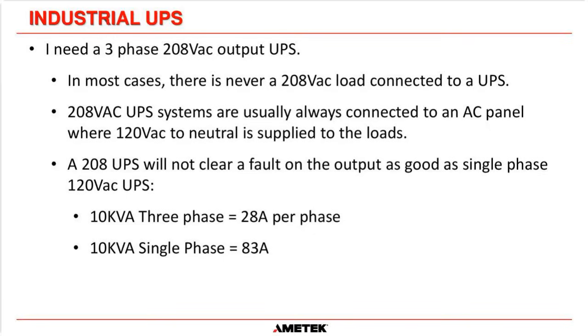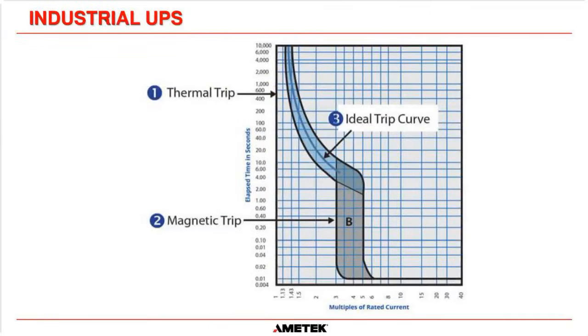Why is that important? Well, you've got to think about it. All of your load circuits are going to be protected either by a breaker or a fuse disconnect system. So let's say that the breaker protecting one of your branches is a 10 amp breaker. In both the 3-phase UPS and the single phase UPS it's a 10 amp breaker. Well, let's go to a trip curve.